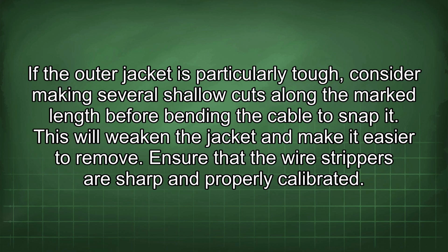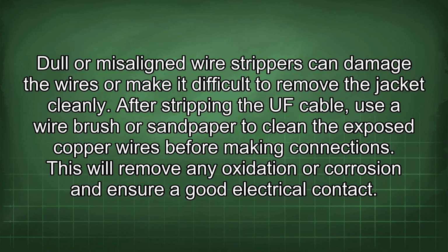Ensure that the wire strippers are sharp and properly calibrated. Dull or misaligned wire strippers can damage the wires or make it difficult to remove the jacket cleanly. After stripping the UF cable, use a wire brush or sandpaper to clean the exposed copper wires before making connections. This will remove any oxidation or corrosion and ensure a good electrical contact.